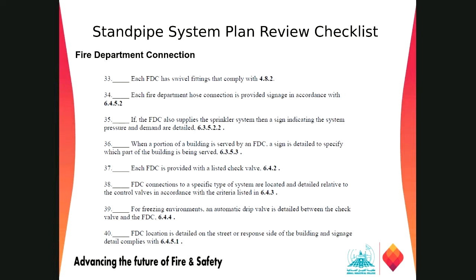Look for the swivel fittings, swivel fitting for the fire department connection as per 4.8.2 of NFPA. The signage for the fire department connection, right? If a fire department connection also supplies a sprinkler system, there should be a sign for pressure and demand at that location. Point number 36 talks about which portion of the building is supplied by this riser, right?